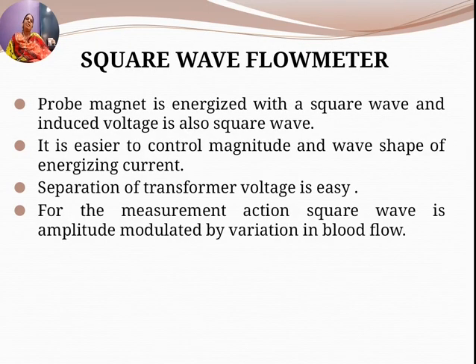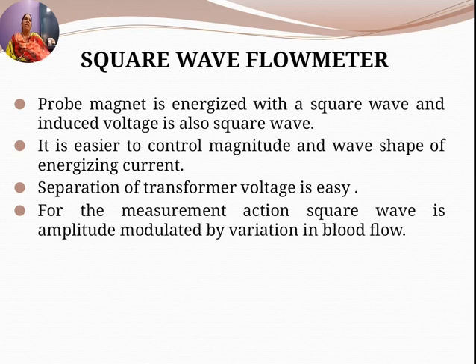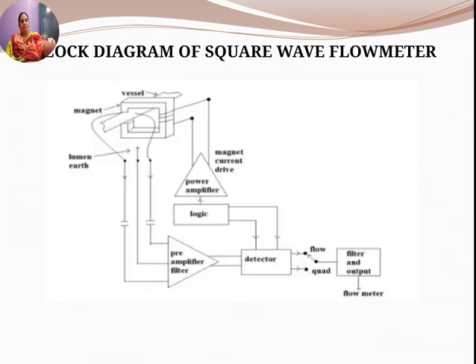When the probe magnet is energized with a square wave and the induced voltage is also a square wave, that type is called a square wave electromagnetic flow meter. It is easier to control the magnitude and wave shape of the energizing current, and separation of transformer voltage is also easier. For the measurement action, the square wave is amplitude modulated by variation in the blood flow.